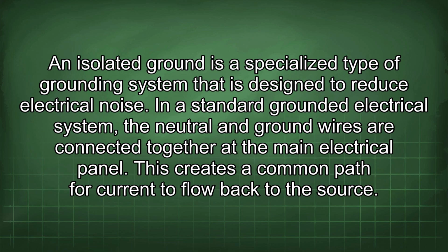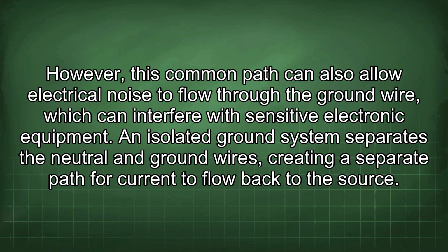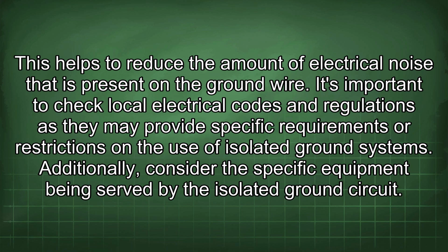An isolated ground is a specialized type of grounding system that is designed to reduce electrical noise. In a standard grounded electrical system, the neutral and ground wires are connected together at the main electrical panel. This creates a common path for current to flow back to the source. However, this common path can also allow electrical noise to flow through the ground wire, which can interfere with sensitive electronic equipment. An isolated ground system separates the neutral and ground wires, creating a separate path for current to flow back to the source. This helps to reduce the amount of electrical noise that is present on the ground wire.